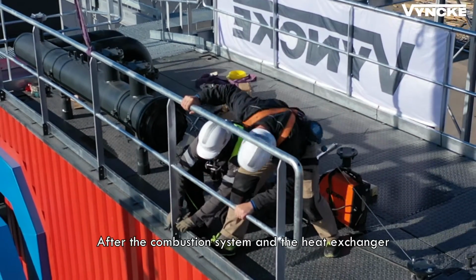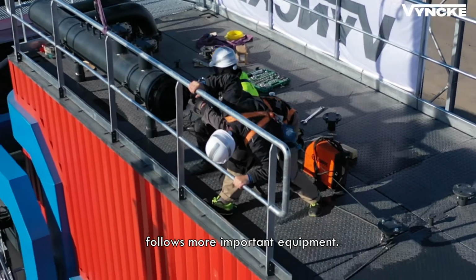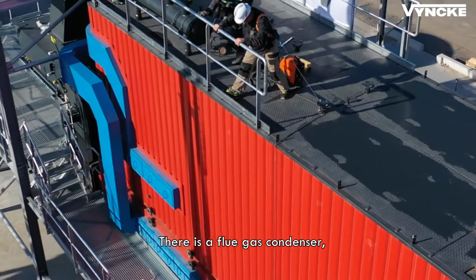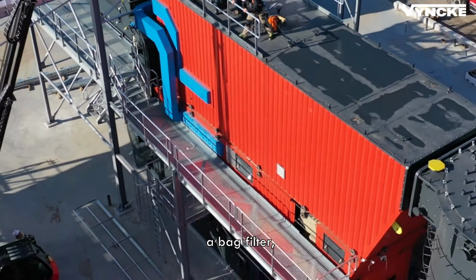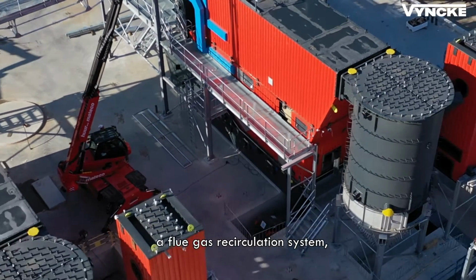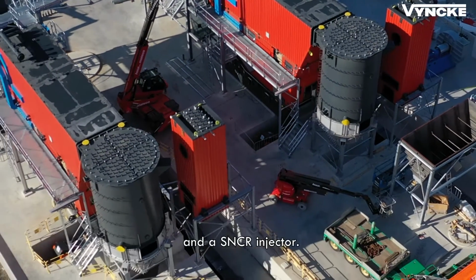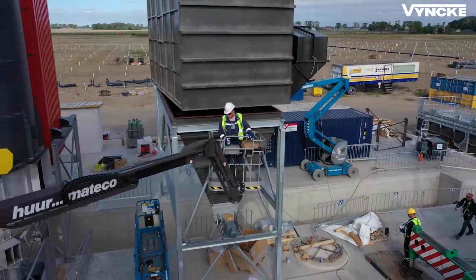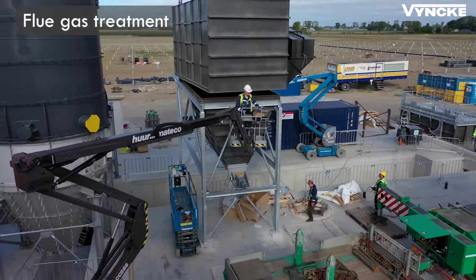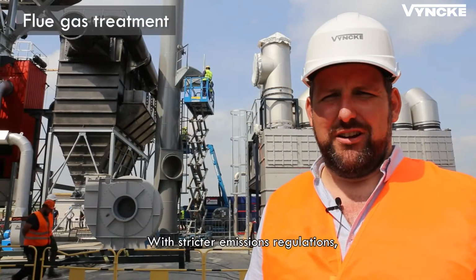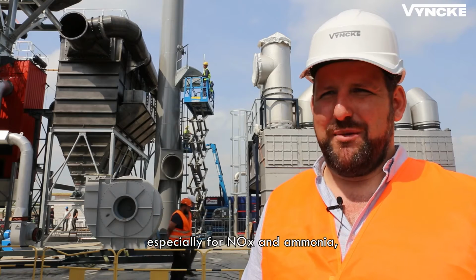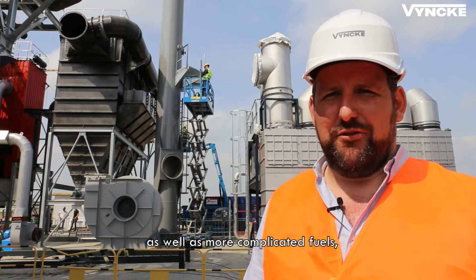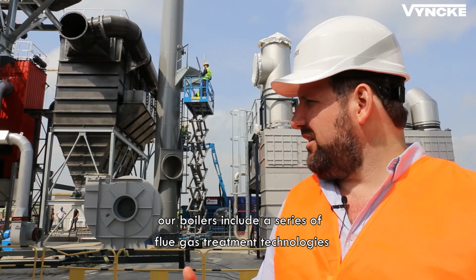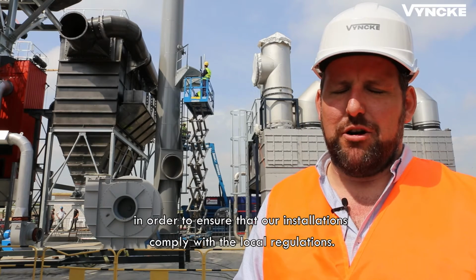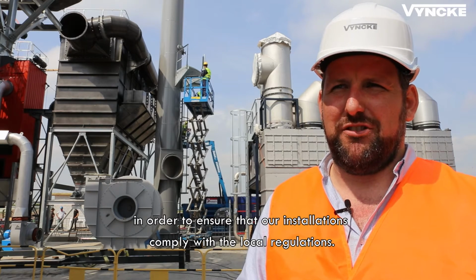After the combustion system and the heat exchanger follows more important equipment. There is a flue gas condenser, a bag filter, a flue gas recirculation system, and a SNCR injector. With stricter emissions regulations, especially for NOx and ammonia, as well as more complicated fuels, our boilers include a series of flue gas treatment technologies in order to ensure that our installations comply with the local regulations.